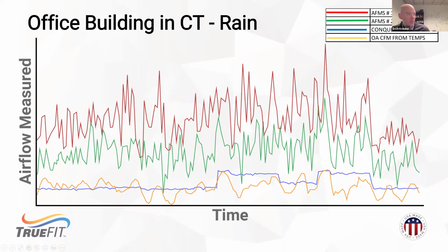Same legend here. So competitors A and B are green and red. The red measurements are everything from 19,000 CFM to 9,000 CFM. So pretty big swings in not a lot of time. Again, we're adding moisture to those thermal dispersion elements, and it's affecting the quality and repeatability of their measurements. For the ASHRAE 111 equation, we see we're pulling in enough moisture where we're also affecting the temperature measurements, but the rough amplitude is, again, right on the blue line. So I'm pretty confident that our numbers are right where they should be.